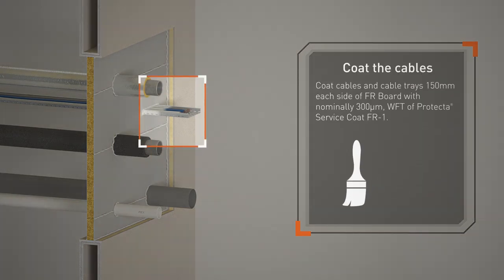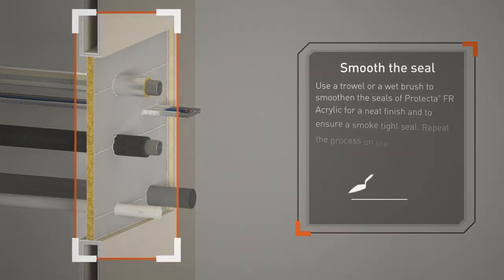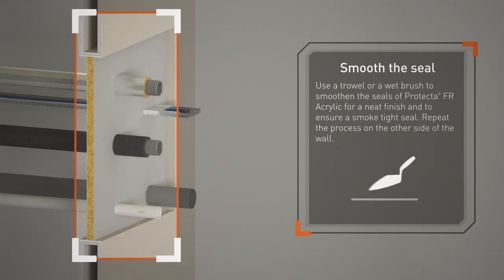Coat cables and cable trays 150mm each side of the FR Board with nominally 300 microns wet film thickness of Protecta Service Coat FR-1. Use a trowel or a wet brush to smooth the seals of Protecta FR Acrylic for a neat finish and to ensure a smoke-tight seal.